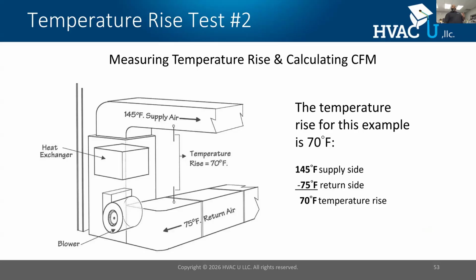And how it looks: I'm going to put a thermometer in a supply duct and a thermometer in a return duct. I often want to put these out of the vision of the heat exchanger. In the heating mode, radiant heat energy can affect my temperature reading, so I want to put it maybe about a foot away. That's where I put mine. I'm going to subtract the return from the supply and get a number. Now you see the 70 degrees Fahrenheit in this application. I'm going to take that 70 and compare it to the bonnet data plate.